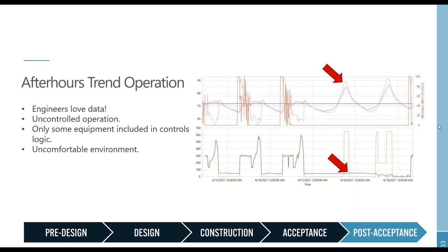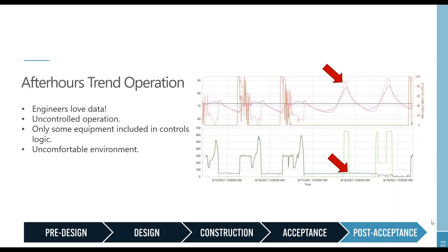So what we discovered in this case was, there was logic implemented to turn on the equipment and have it maintain a comfortable temperature during those unoccupied hours. What actually happened was that was only applicable to half the spaces. And the logic that they had implemented did not include it for every part of the building.